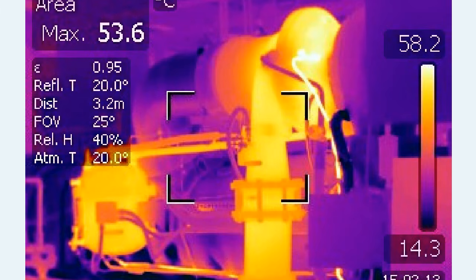And I've also got a thermal image from one of the chillers we were working on previously. And as you can see from here, the discharge line is coming down here with the suction line here, and this is the hot, compressed refrigerant coming out and entering off into the condenser.